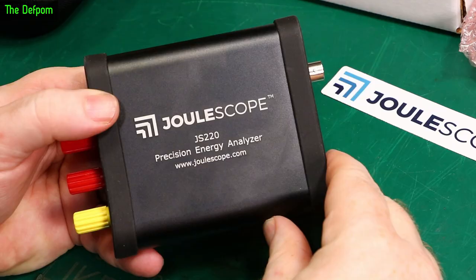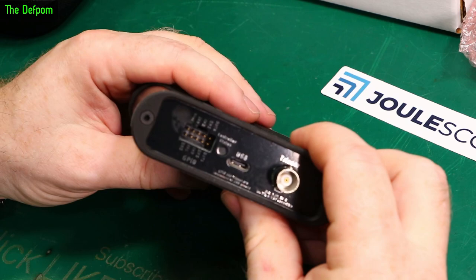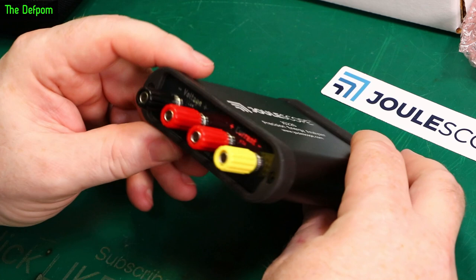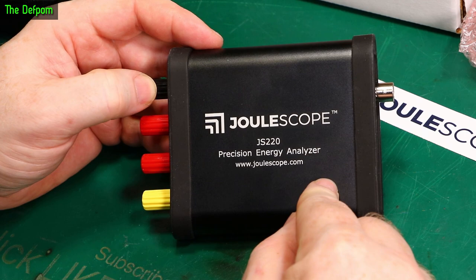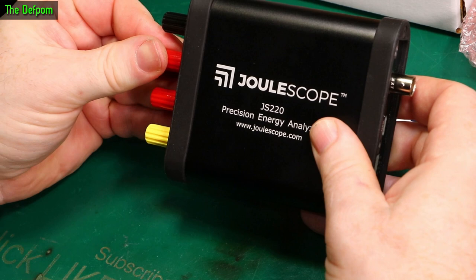So let's move the case out of the way. And here it is. Precision Energy Analyzer. This is an upgrade over the JS110, which has been sold for a little while now. This is the same price as that unit. Price hasn't changed, but this has got better specs and better features. This is a 16-bit vertical resolution instead of 14-bit on the previous version. And this has got a larger dynamic range on voltage and current.